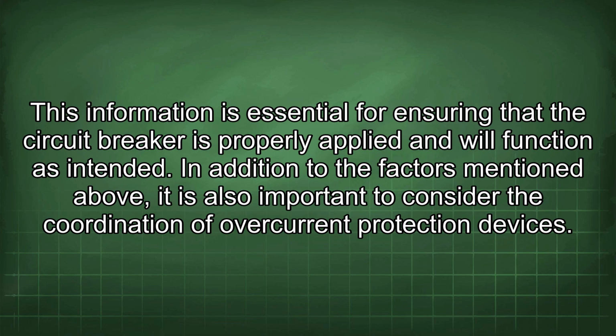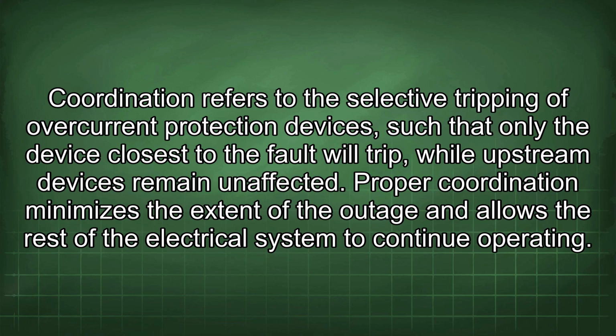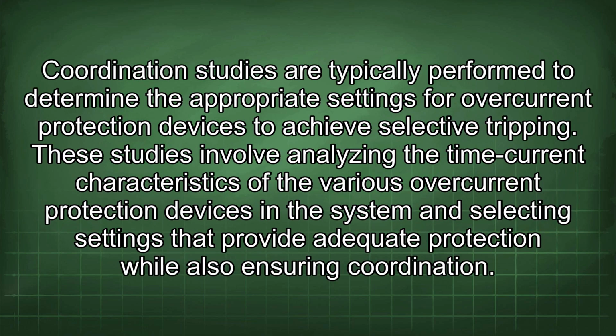In addition to the factors mentioned above, it is also important to consider the coordination of overcurrent protection devices. Coordination refers to the selective tripping of overcurrent protection devices such that only the device closest to the fault will trip, while upstream devices remain unaffected. Proper coordination minimizes the extent of the outage and allows the rest of the electrical system to continue operating. Coordination studies are typically performed to determine the appropriate settings for overcurrent protection devices to achieve selective tripping. These studies involve analyzing the time current characteristics of the various overcurrent protection devices in the system and selecting settings that provide adequate protection while also ensuring coordination.